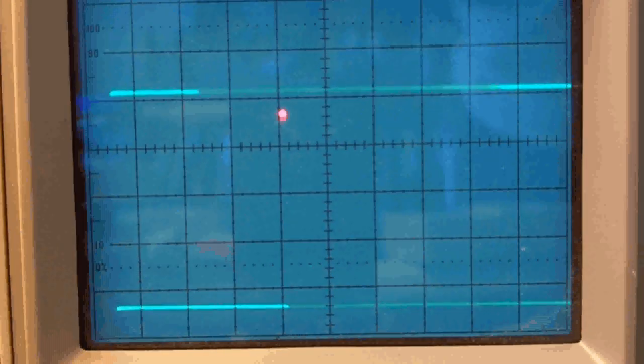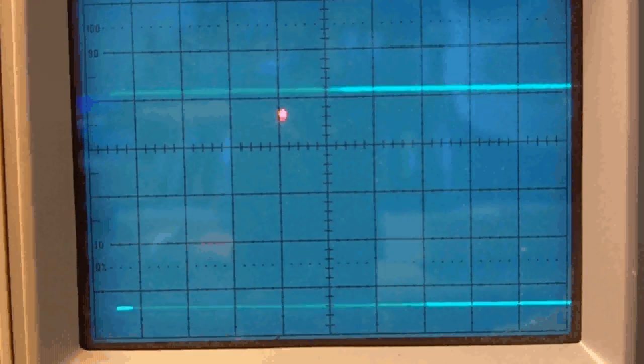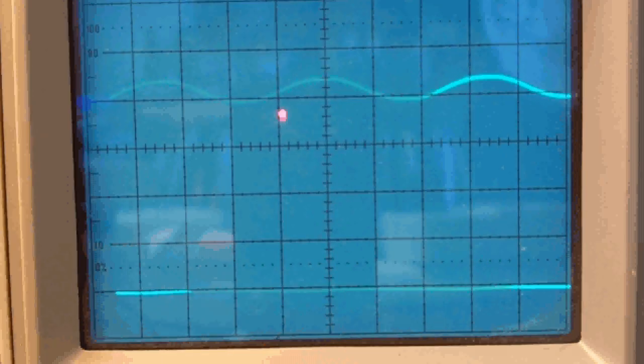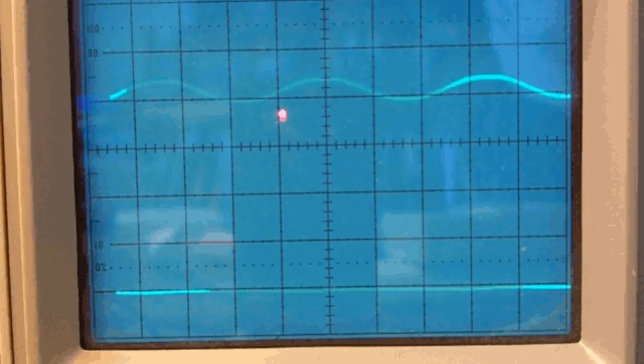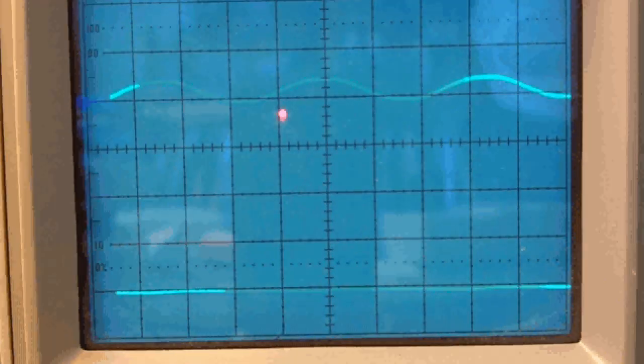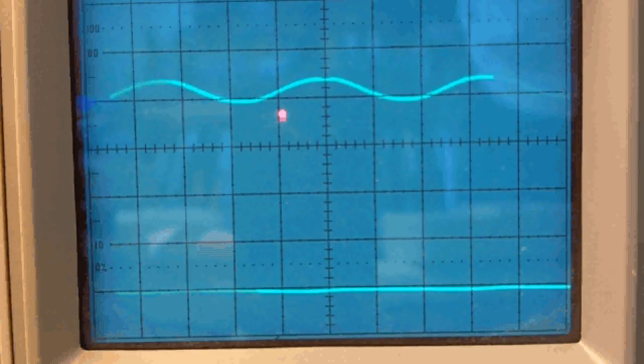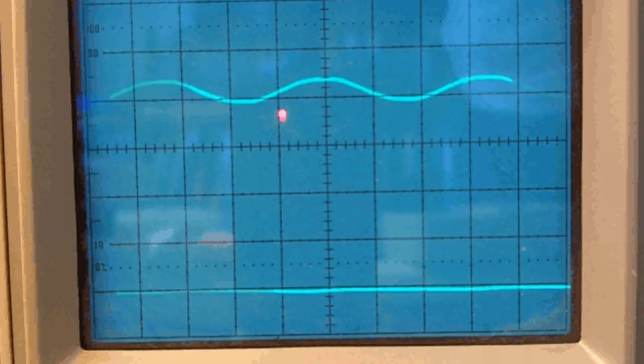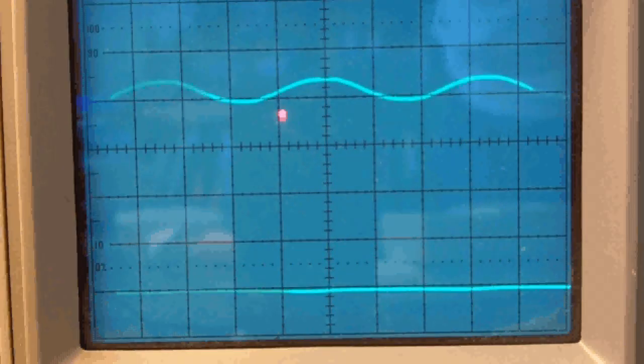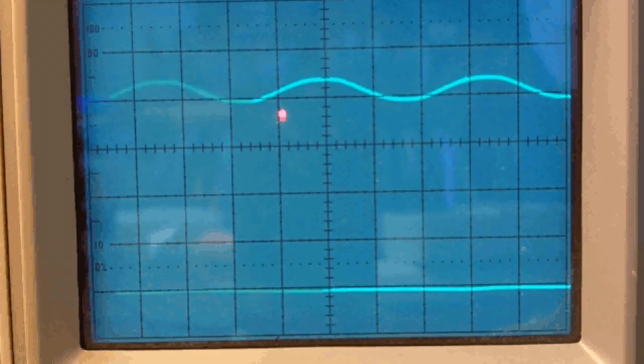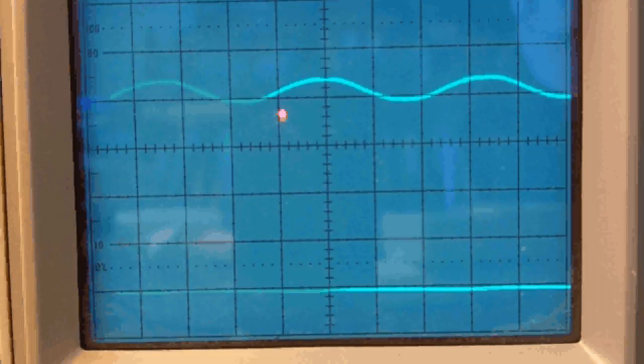So let me turn on the lamp to the first position, the 50 watt bulb. The amperage is again .45. The raw signal value is 2.6. And the signal now after the signal condition is about .62. A nice steady line with no fluctuation that would be easy for the microprocessor to read.